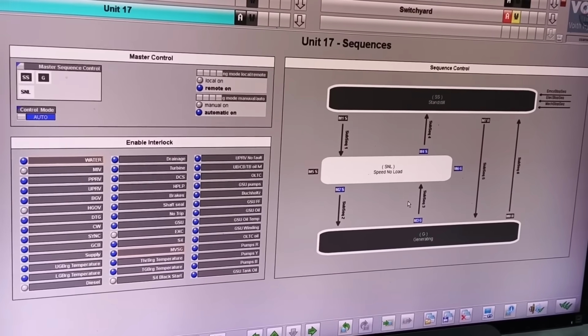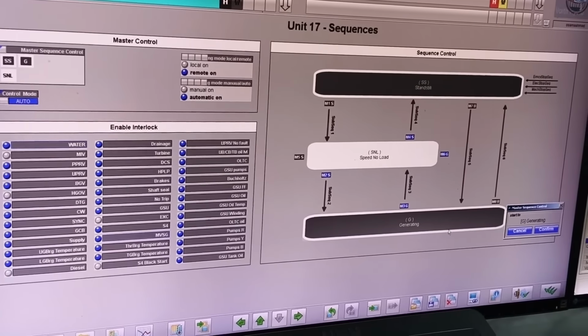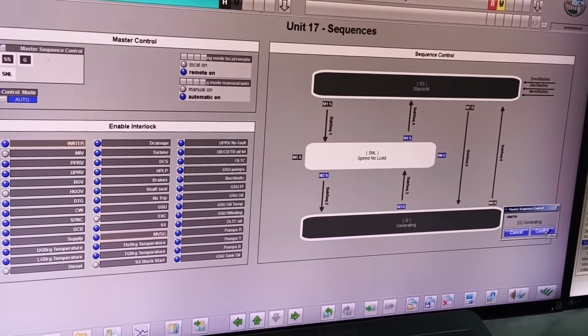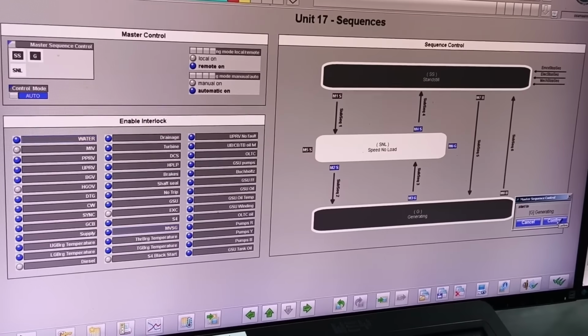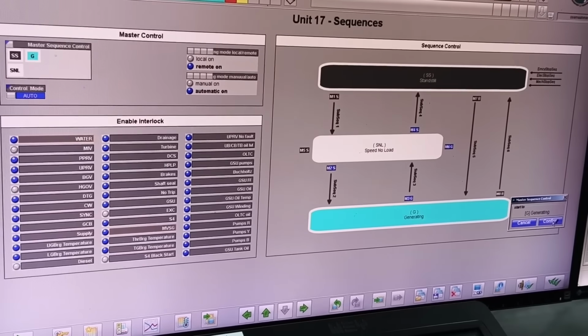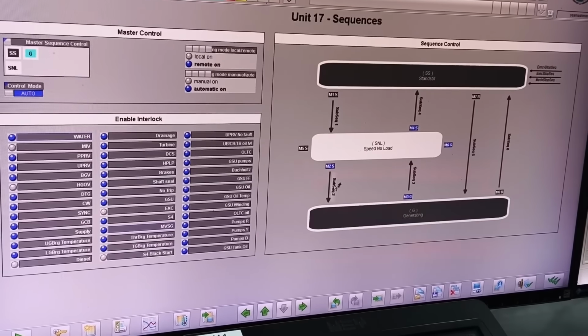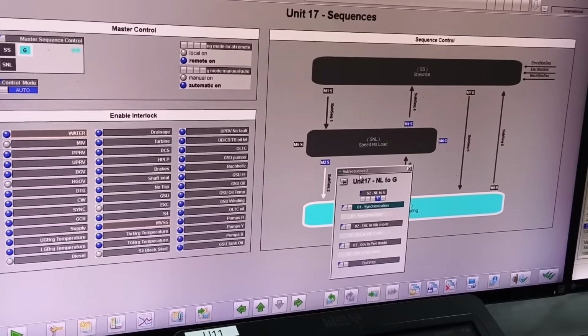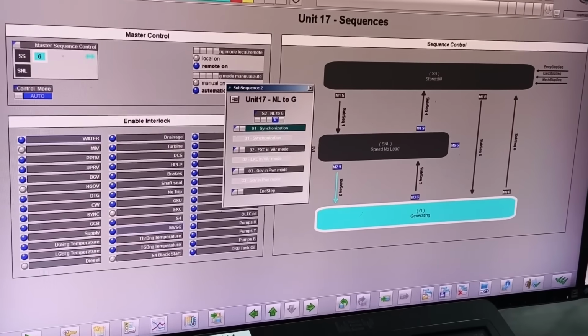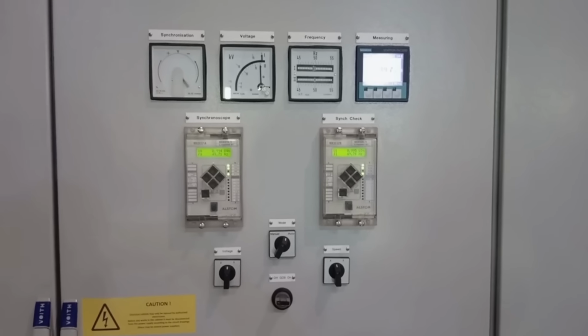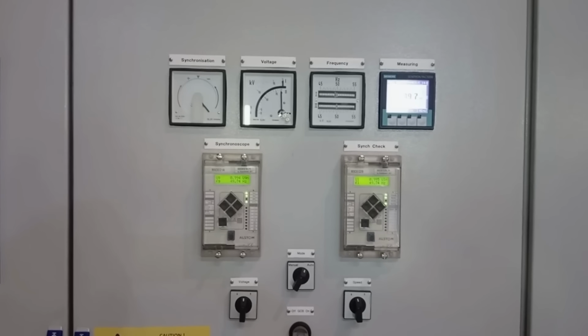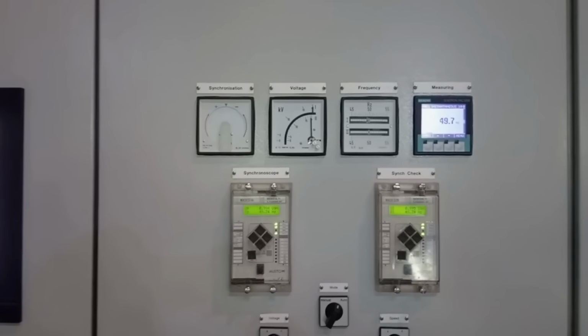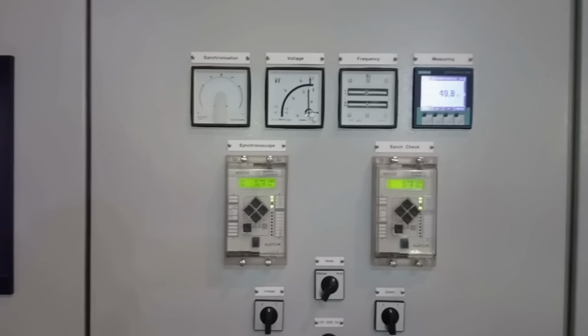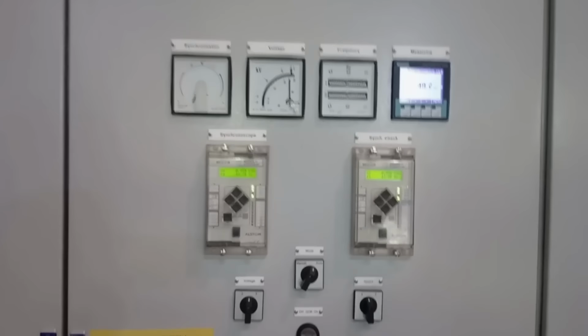And then the final step is synchronization and generation. Now comes the final command. The operator gives the final command of synchronization. The governor stabilizes turbine speed. The excitation system stabilizes voltage. Meanwhile, the protection system continuously monitors vibration, bearing temperature, oil pressure, cooling water, shaft condition, and electrical parameters in real time. So everything must match perfectly: frequency, voltage, phase angle, and grid connection.